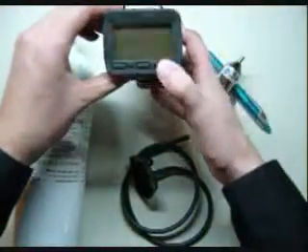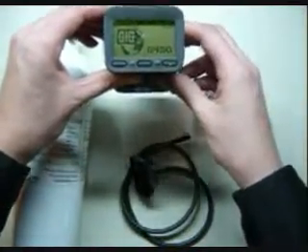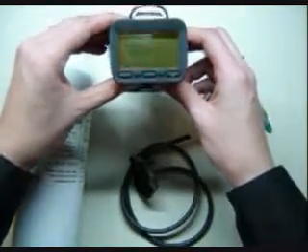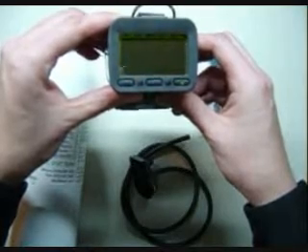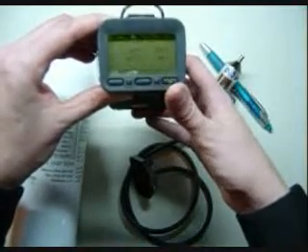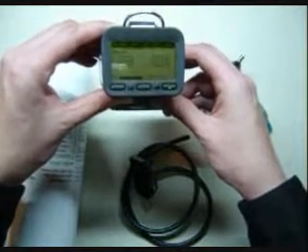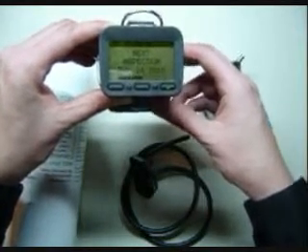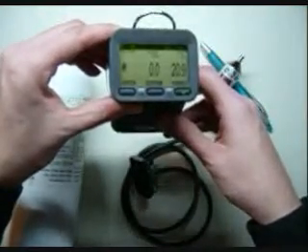First step is going to be turning your monitor on. Hold the button on the right for a few seconds — it will beep — and then it will go through the startup check. This process goes through just about everything on the monitor. Next inspection data is just when you send it back either to your person you purchased it from or a registered repair center with GFG.